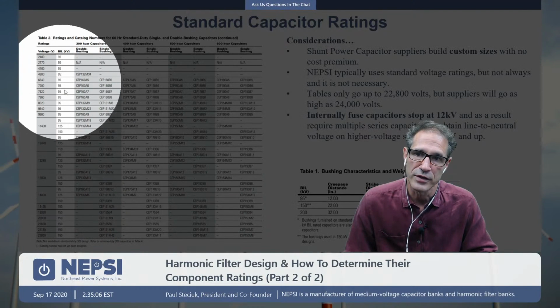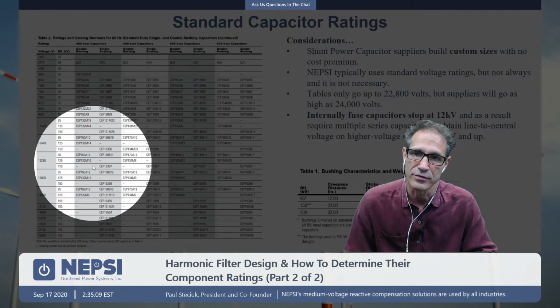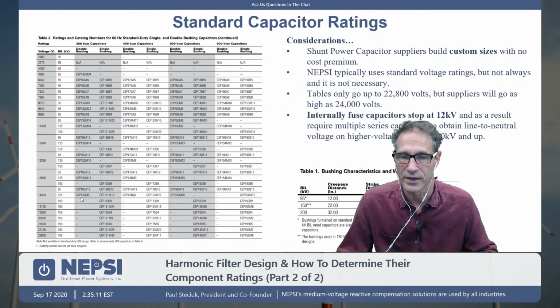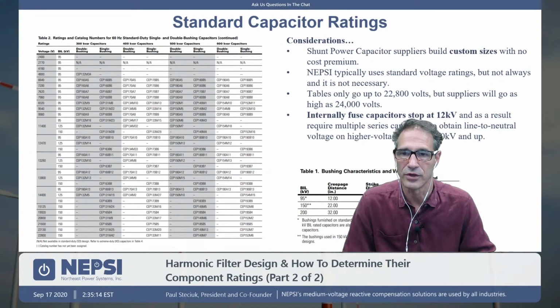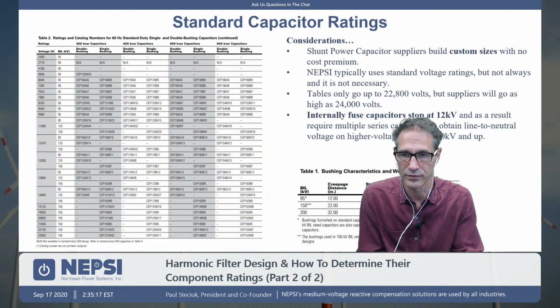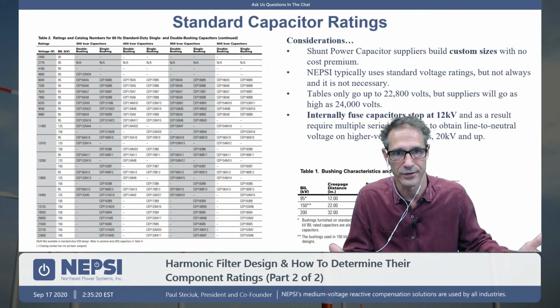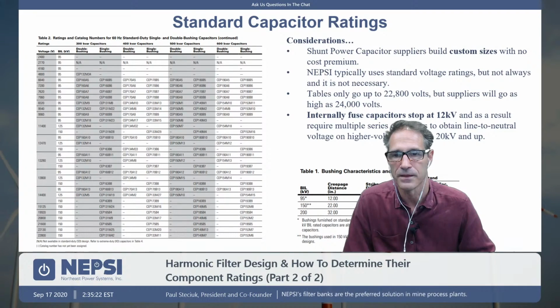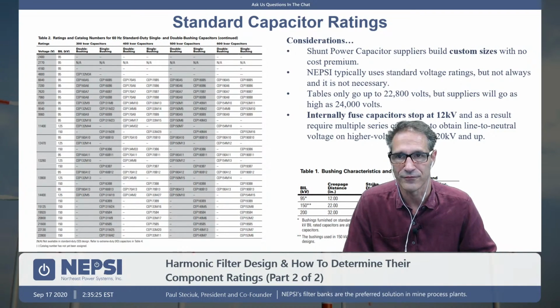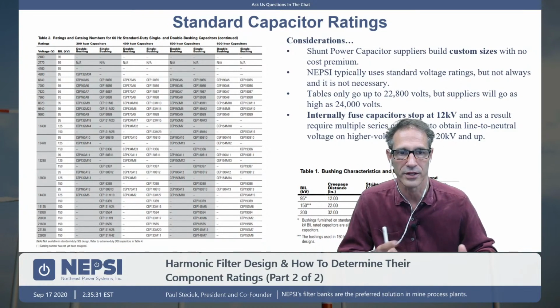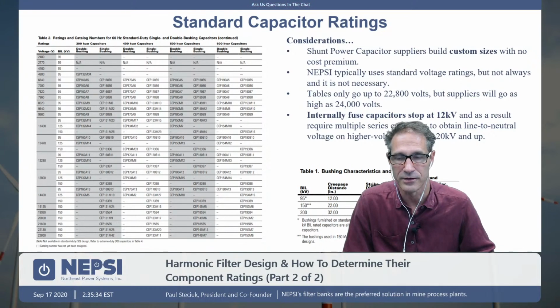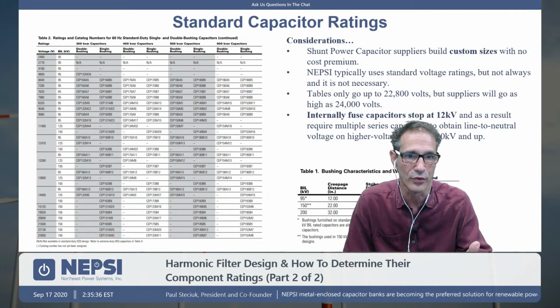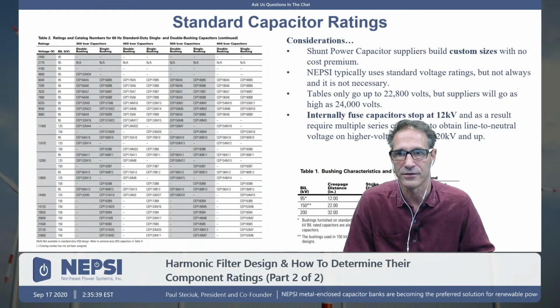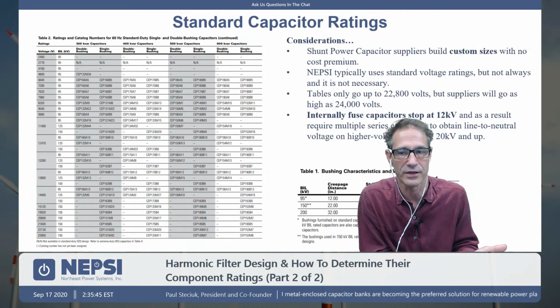These are the voltage ratings and the kVAR ratings for the capacitors. They're the standard ratings. You can ask for basically any kVAR rating you want. Obviously, as you go up in kVAR, the can is getting bigger and bigger, so heavier and heavier. There are some limits from the supplier of the capacitor: typically at the 15 kV level you're looking at maybe 600 kVAR, and at the 2.4 kV level you're looking at just 200 kVAR per can. So, depending upon the voltage level of the capacitor, you're able to get a certain size can.